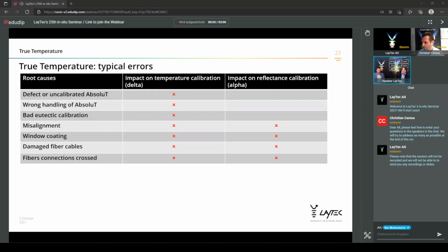What can also happen sometimes is that the fiber connections, typically at the fiber optical head of the APTT, can accidentally be crossed. This can easily happen if you don't pay attention when you disconnect the fiber cables from the head, maybe for cleaning the reactor lid area or the glove box, or for repair work or leak tests. If you reconnect them and don't pay attention to the correct placement, you can easily cross the connections. Typically, the fiber cables are marked by clips right at the end where the connector connects to the fiber optical head. It indicates the fiber cables that feed the light from the light source, and the fiber cable that receives the light back to the controller, to the detector.